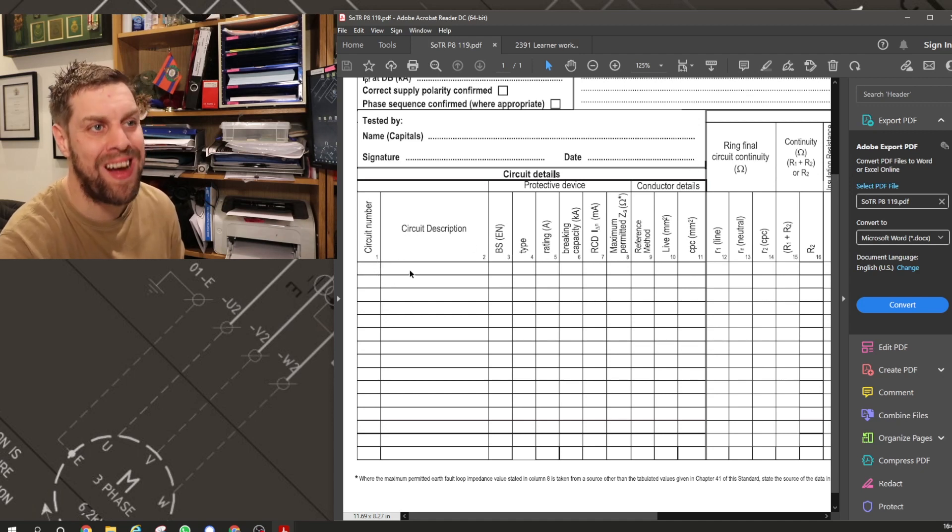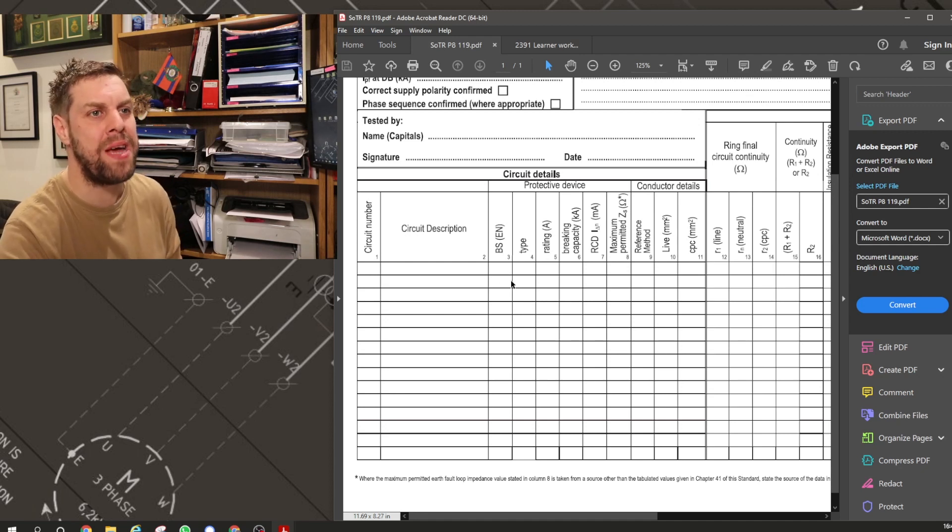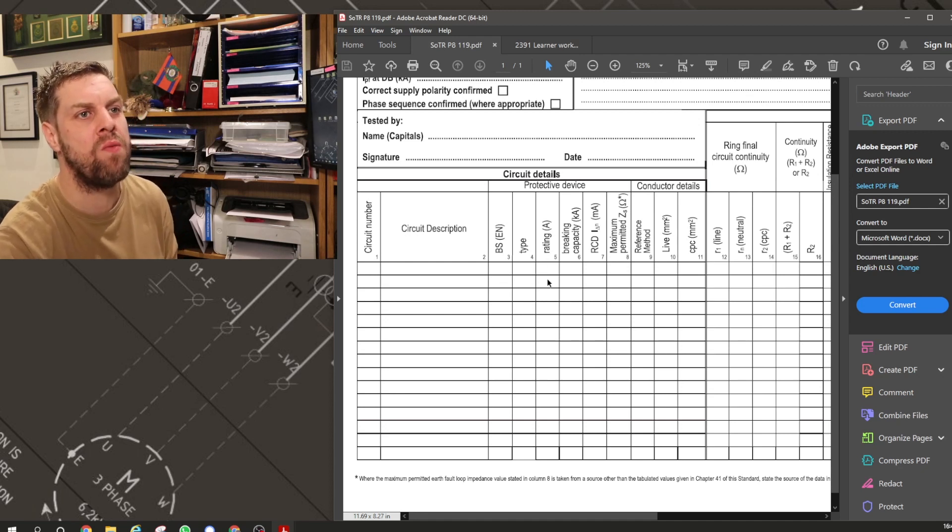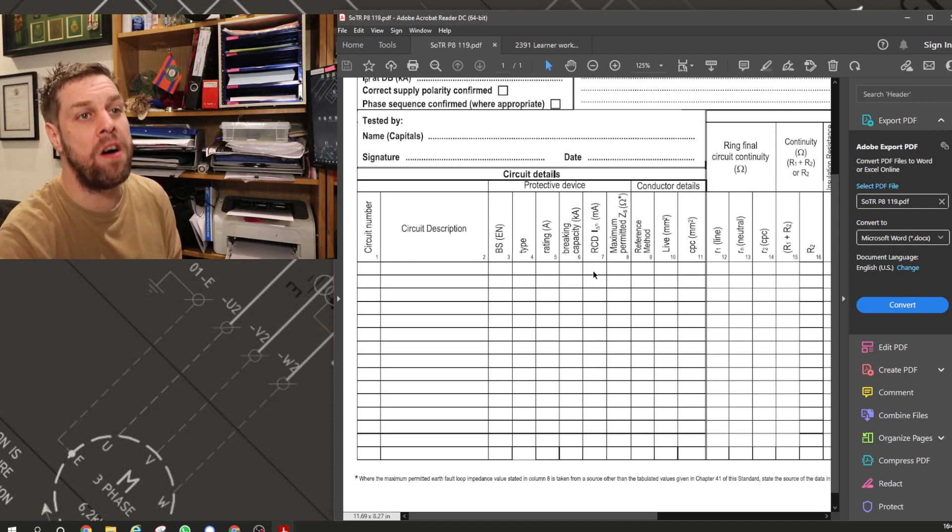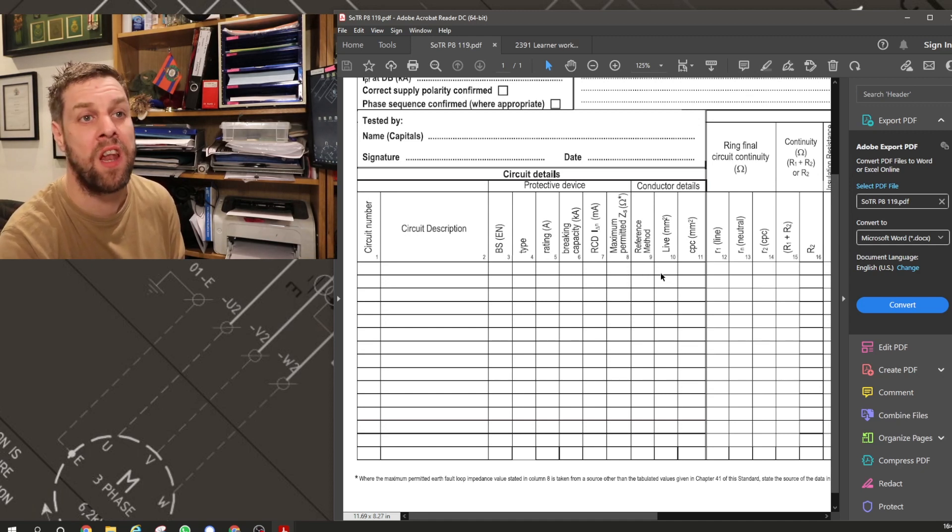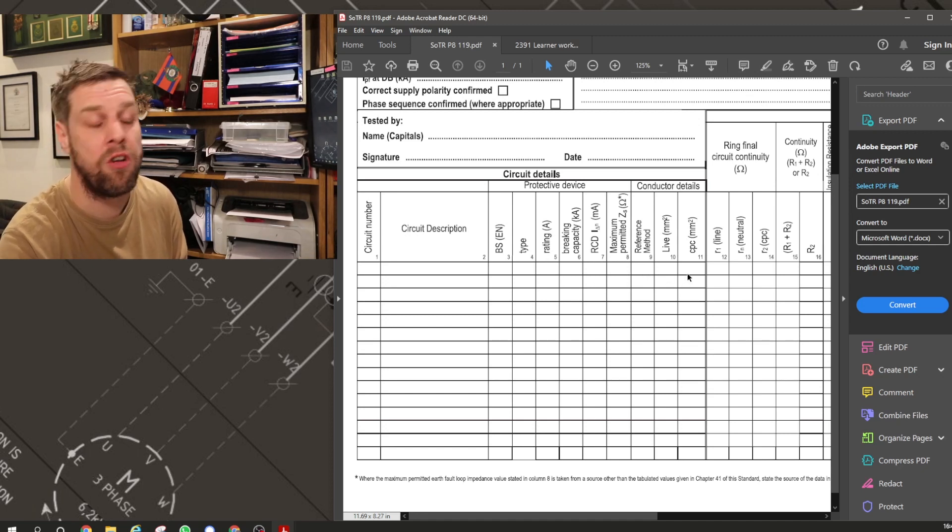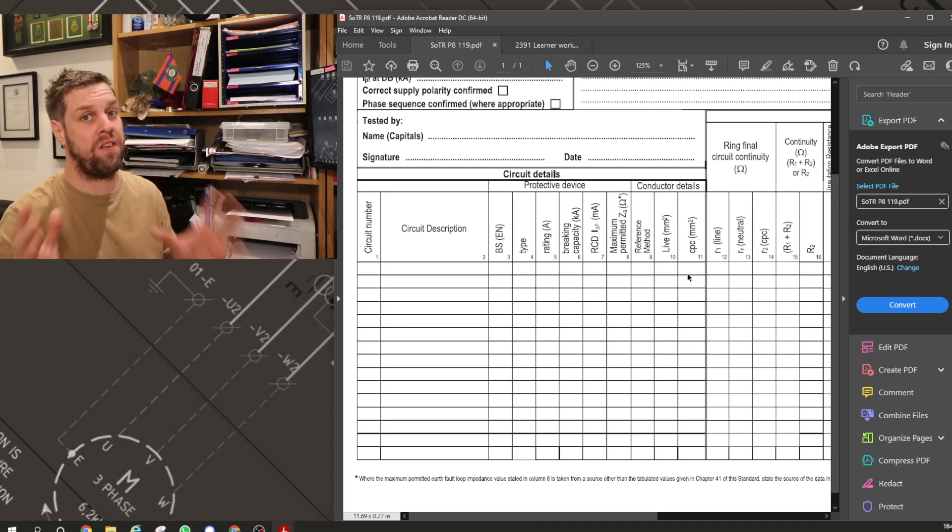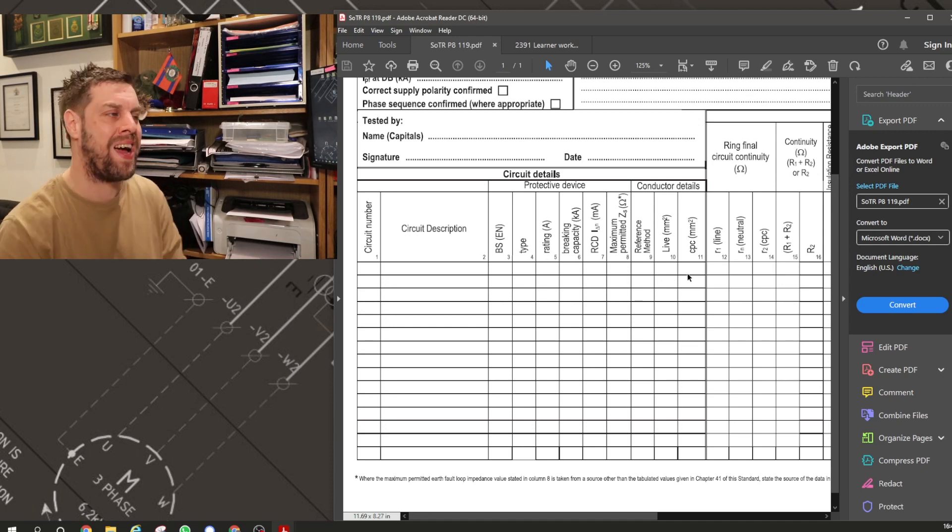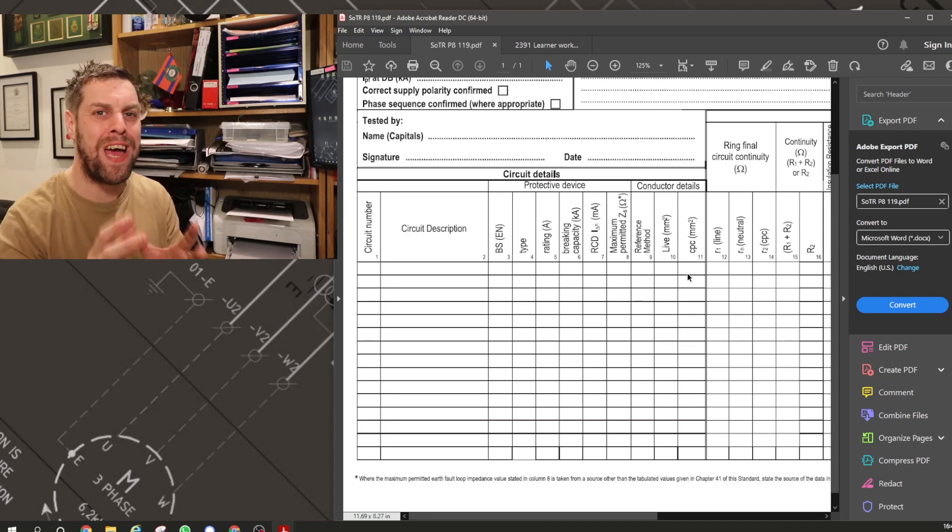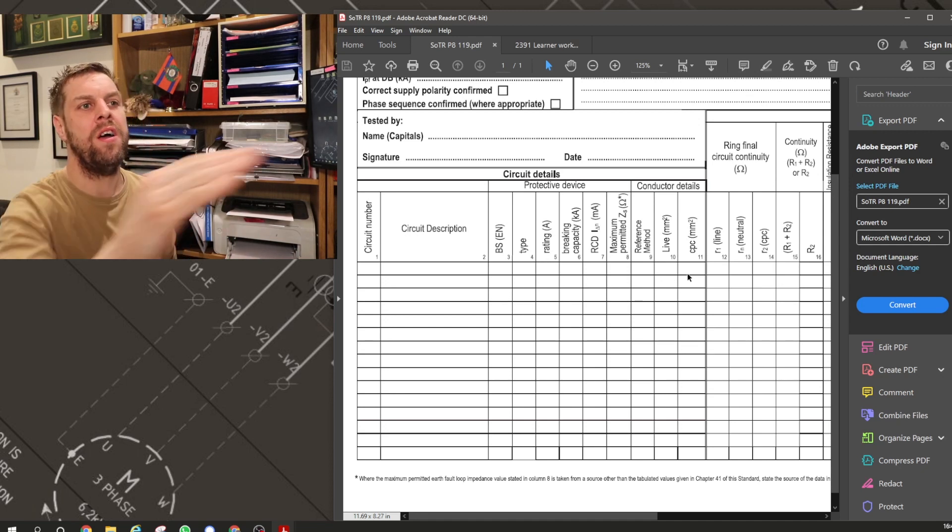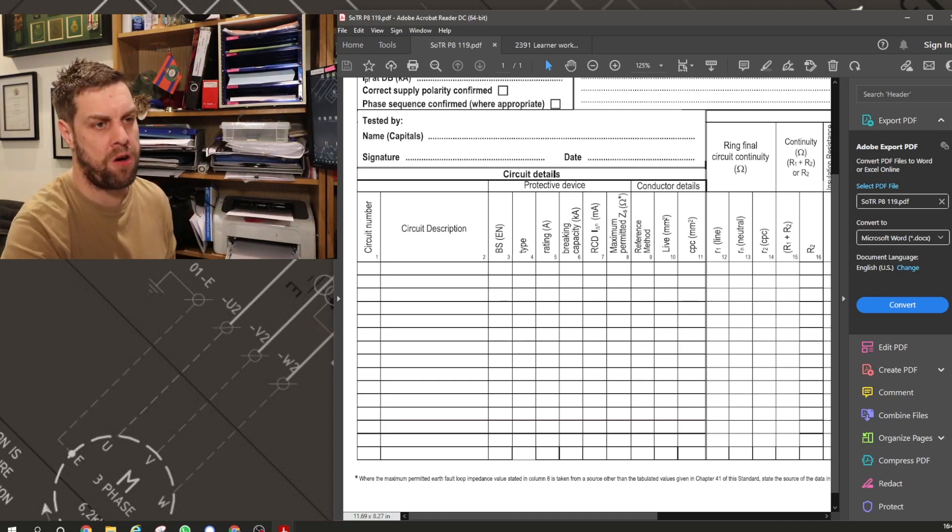The circuit number, you gather that. The description, you gather that. The BS and the type, the rating, the breaking capacity, the RCD milliamp, the maximum Zs, the reference method, the live and the earth size. Brown books on that, yeah? You gather that information. That's just data you acquire. You can fill all that in before you start.